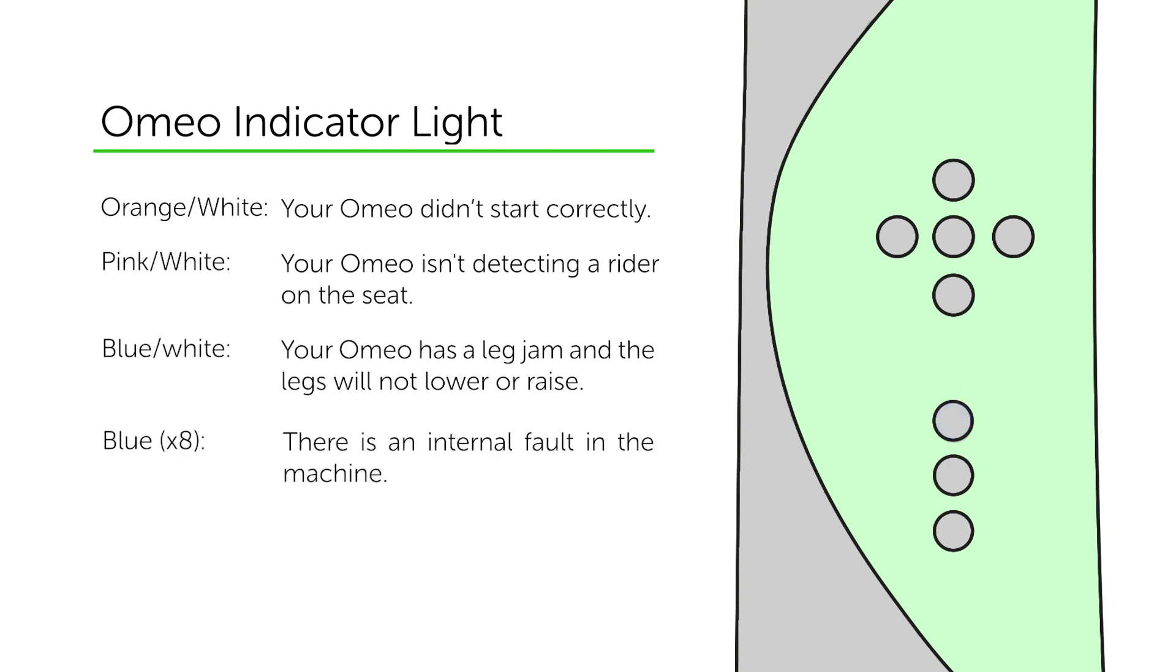If your light is flashing blue in a sequence of 8, this is due to an internal fault in the machine. The long flash in the sequence is the fault number. You should power down your machine and follow the troubleshooting guide found in your Omeo manual. You should also get in contact with your Omeo agent.